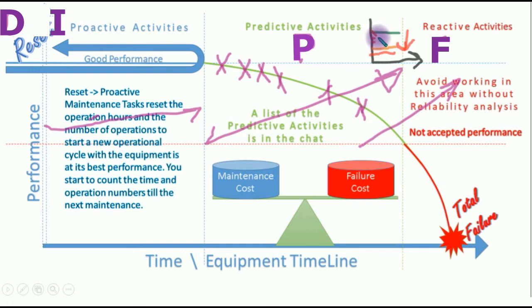Still, that's not available for every equipment — because during operation, the status of the machine is totally different from the status during stoppage, especially for electrical equipment. During a high-power substation, the stress and load on the equipment is totally different. When you shut it down completely and make safety conditions and go inside to inspect while the equipment is cooled, you will not get any indication unless you check every bolt and nut in the high-voltage area. But the pump — as I told you — you will have the pressure falling a little bit. That's a free indication.